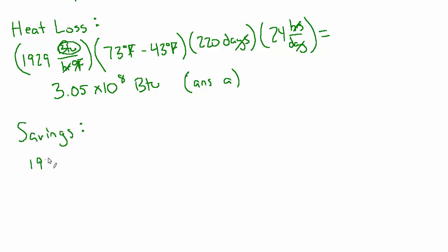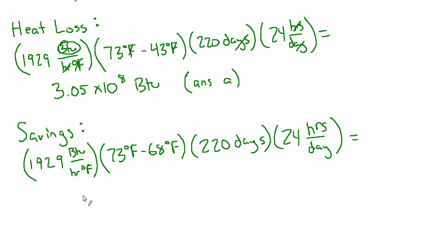So it's still 1929 BTU per hour per degree F. But now the delta T is going to be 5. So we'll say 73 degrees minus 68 degrees. This is just the savings. And the time is the same. It's still 220 days and still 24 hours per day. And that works out to 5.1 times 10 to the 7th BTUs. And that's answer B.